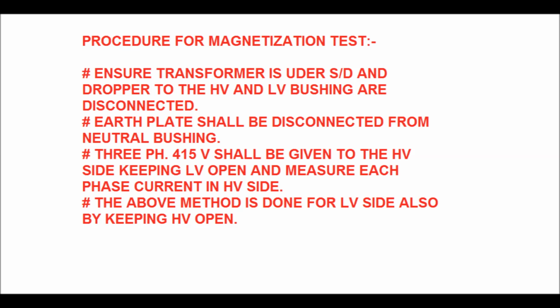The 3-phase supply should be given through a fuse or MCB, because if a transformer is found to be defective, it will draw more magnetizing current, and therefore it can harm the winding of the transformer.